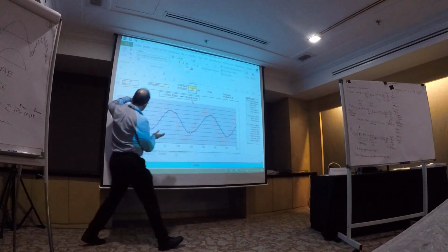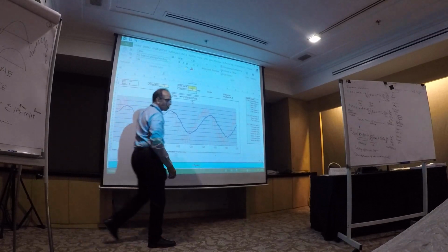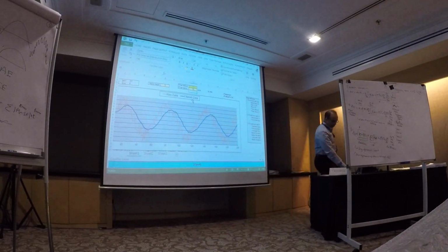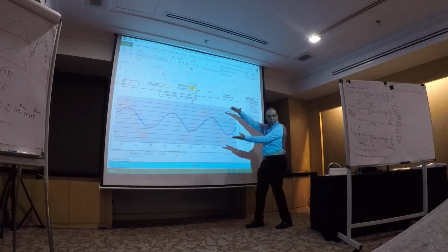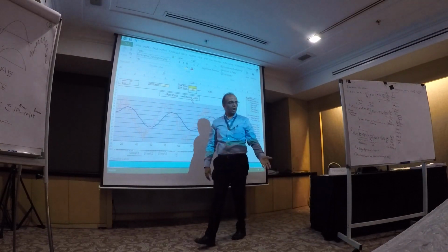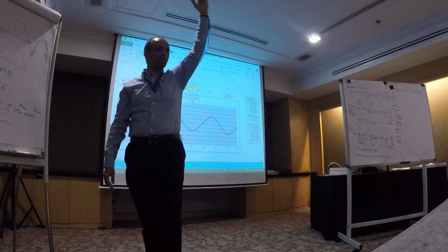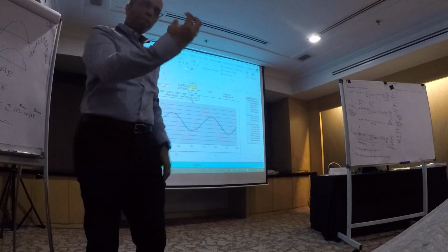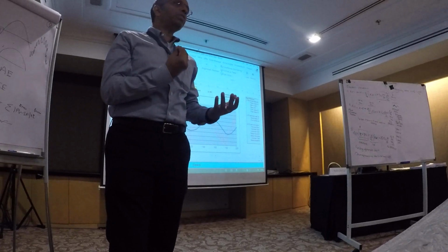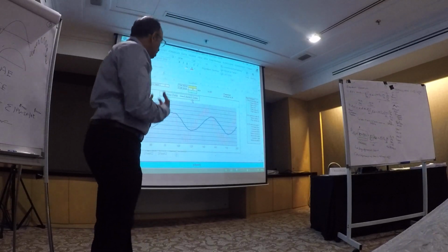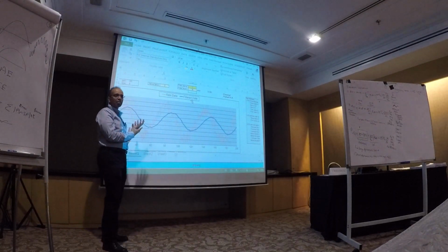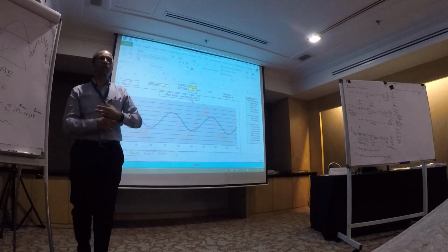Right? So you notice that the peak to peak now, so if I started at, say, 3 seconds just now, I get a high output. Let's say I put 15. You're starting to see it shrink. So even though your output reaches a high level, say it's reaching 100 tons per day, but your measured value that you see on the DCS, if you apply too much of a filter, you may only get 80 or 90 tons per day.